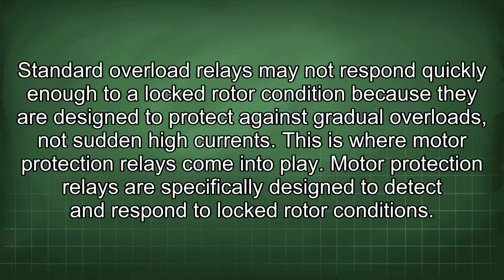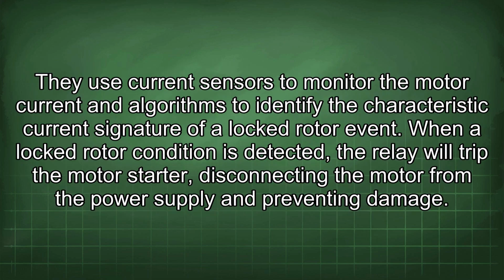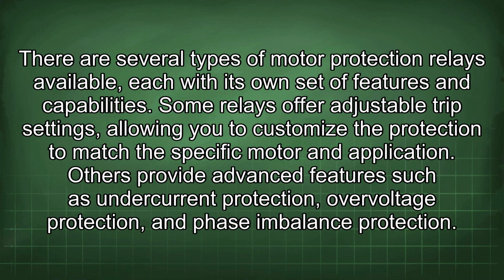Motor protection relays are specifically designed to detect and respond to locked rotor conditions. They use current sensors to monitor the motor current and algorithms to identify the characteristic current signature of a locked rotor event. When a locked rotor condition is detected, the relay will trip the motor starter, disconnecting the motor from the power supply and preventing damage. There are several types of motor protection relays available, each with its own set of features and capabilities. Some relays offer adjustable trip settings, allowing you to customize the protection to match the specific motor and application. Others provide advanced features such as undercurrent protection, overvoltage protection, and phase imbalance protection.